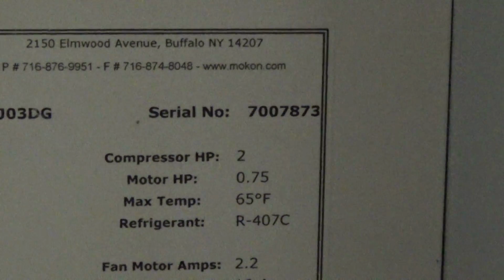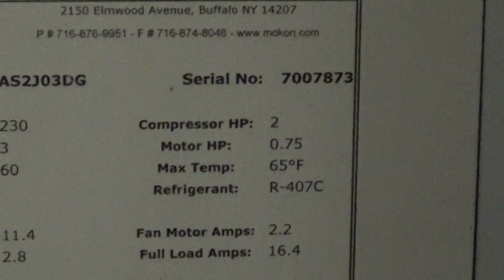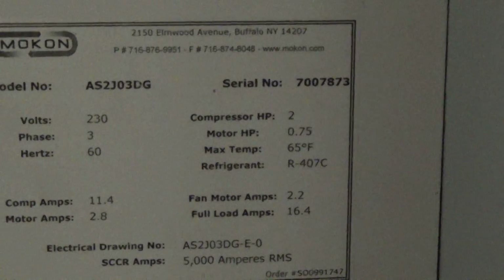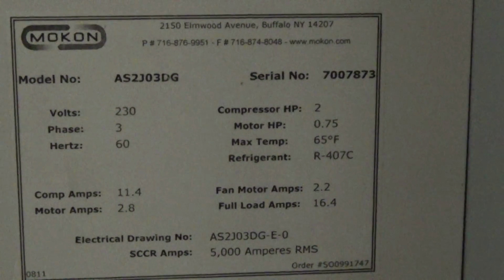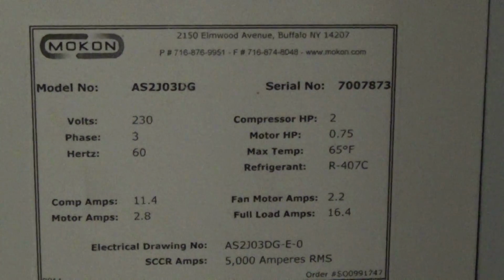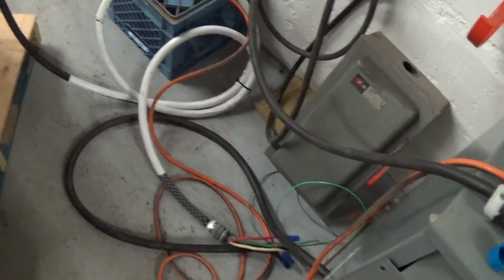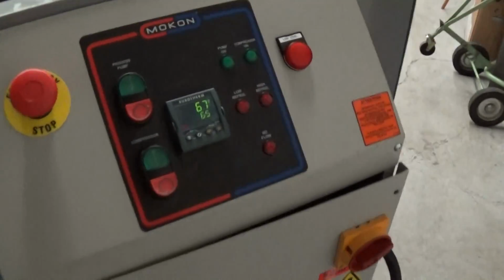Serial number 7007873 with a 3/4 horsepower pump. It's our 407C refrigerant, 230 volt 3-phase. So first thing we're going to do is turn on our main power here. And this comes with a cable, but not a plug. We got this with that cable.